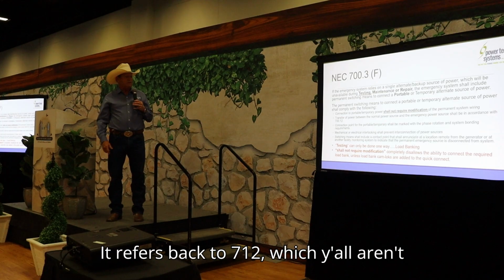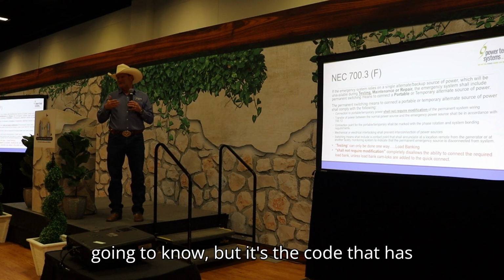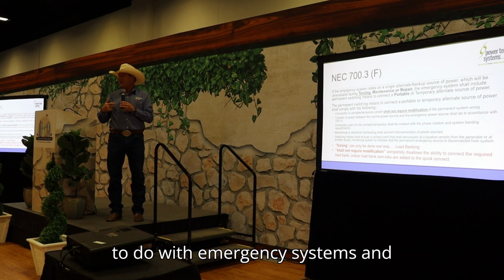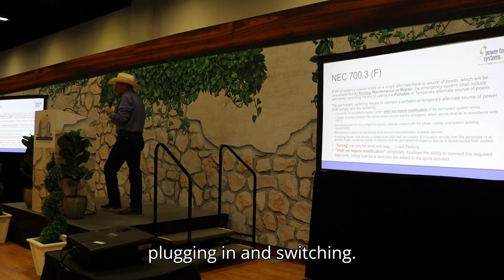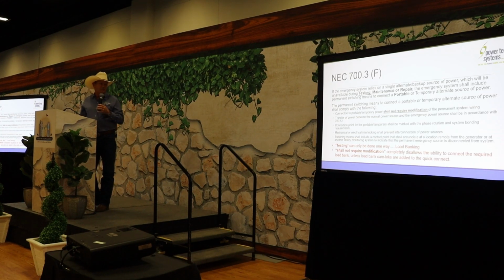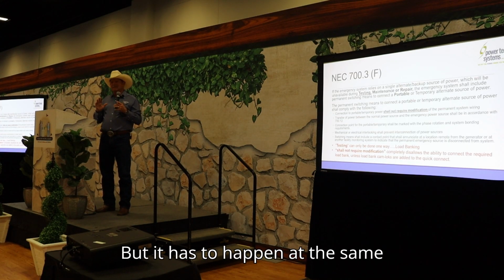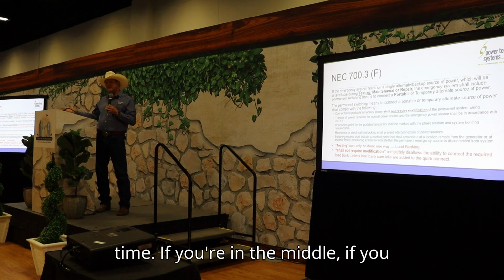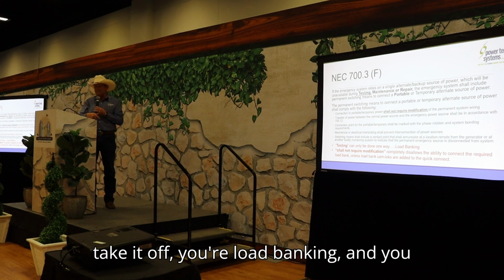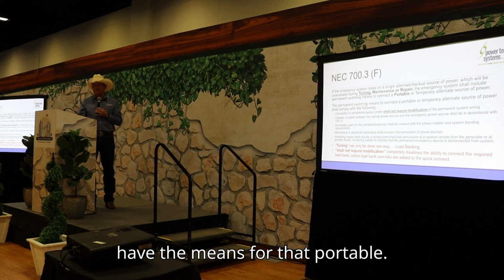It refers back to 712, which y'all aren't going to know, but it's the code that has to do with emergency systems, plugging in and switching. It has to happen at the same time. If you're in the middle of load banking and you don't have backup anymore, you have to have the means for that portable.